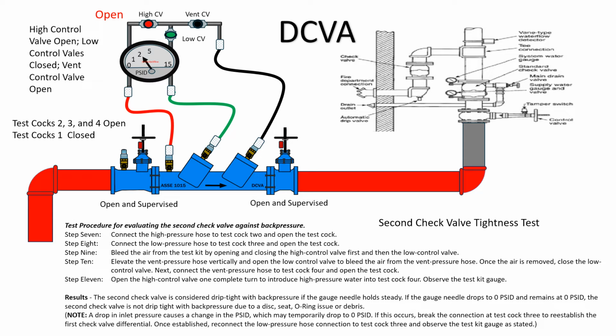Note, a drop in inlet pressure causes a change in the psid, which may temporarily drop to 0 psid. If this occurs, break the connection at test cock 3 to re-establish the first check valve differential. Once established, reconnect the low-pressure hose connection to test cock 3, and observe the test kit gauge as stated.